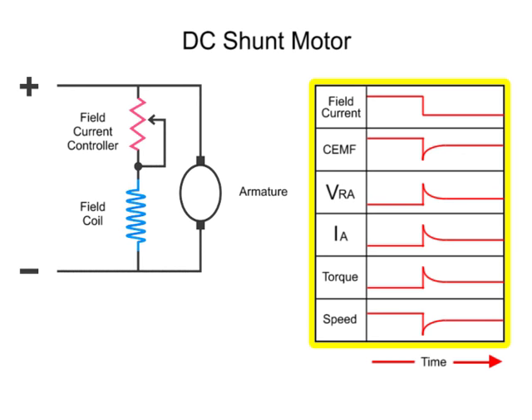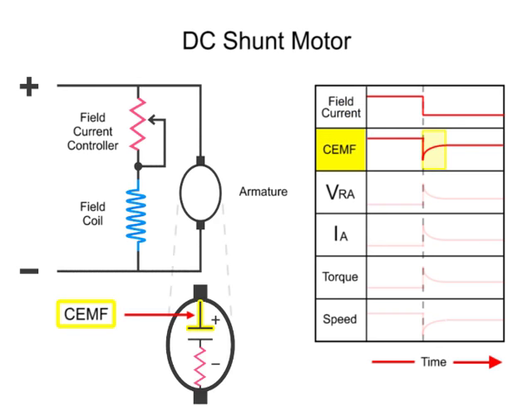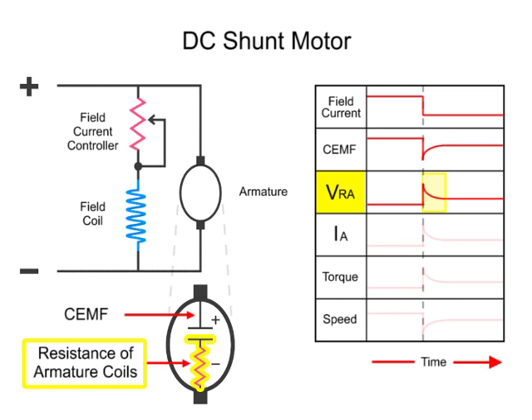Here, we have a series of line diagrams to illustrate the relationships of the motor properties as a result of reducing current to the field. When the field current is decreased, the counter-electromotive force, or CEMF, drops off dramatically. This sudden change results from a reduction in the EMF generated in the armature coils, which are turning within a less dense magnetic field. The less dense magnetic field is a result of the lowered field current flow. This also causes a spike in the voltage drop across the resistance of the armature.